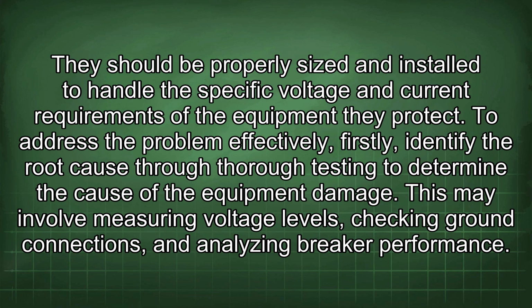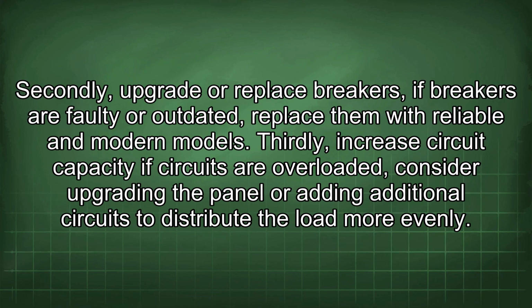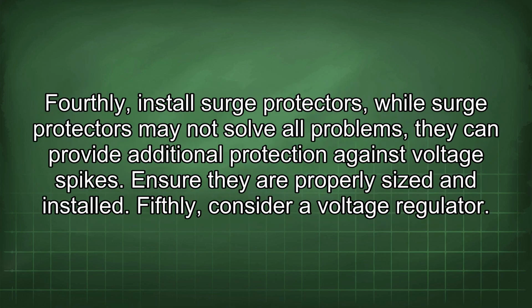To address the problem effectively, firstly, identify the root cause through thorough testing to determine the cause of the equipment damage. This may involve measuring voltage levels, checking ground connections, and analyzing breaker performance. Secondly, upgrade or replace breakers. If breakers are faulty or outdated, replace them with reliable and modern models. Thirdly, increase circuit capacity. If circuits are overloaded, consider upgrading the panel or adding additional circuits to distribute the load more evenly. Fourthly, install surge protectors.